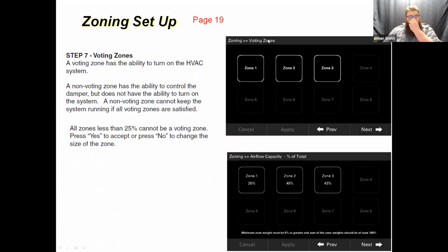Okay. Once it's done doing your AutoZone airflow capacity, you'll see this screen down here at the bottom where it'll give you your zone sizes. So in this particular case, we've got a 43, a 40, and a 20% zone. If you accept those, it then gives you the option to make those voting zones or non-voting zones. So any zone that's less than 25%, so this zone 1, cannot be selected as a voting zone. It requires each zone to be at least 25% in order to be a voting zone.